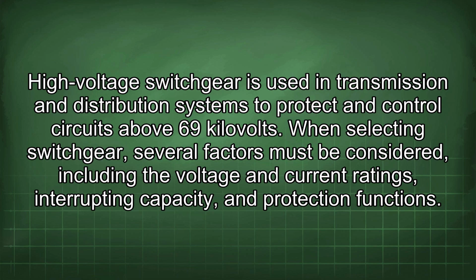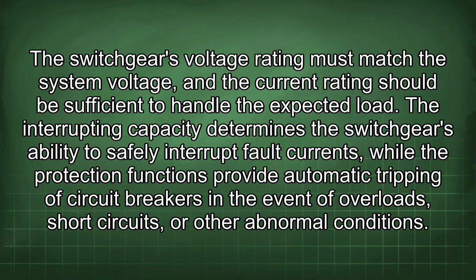High voltage switchgear is used in transmission and distribution systems to protect and control circuits above 69 kV. When selecting switchgear, several factors must be considered, including the voltage and current ratings, interrupting capacity, and protection functions. The switchgear's voltage rating must match the system voltage, and the current rating should be sufficient to handle the expected load. The interrupting capacity determines the switchgear's ability to safely interrupt fault currents, while the protection functions provide automatic tripping of circuit breakers in the event of overloads, short circuits, or other abnormal conditions.